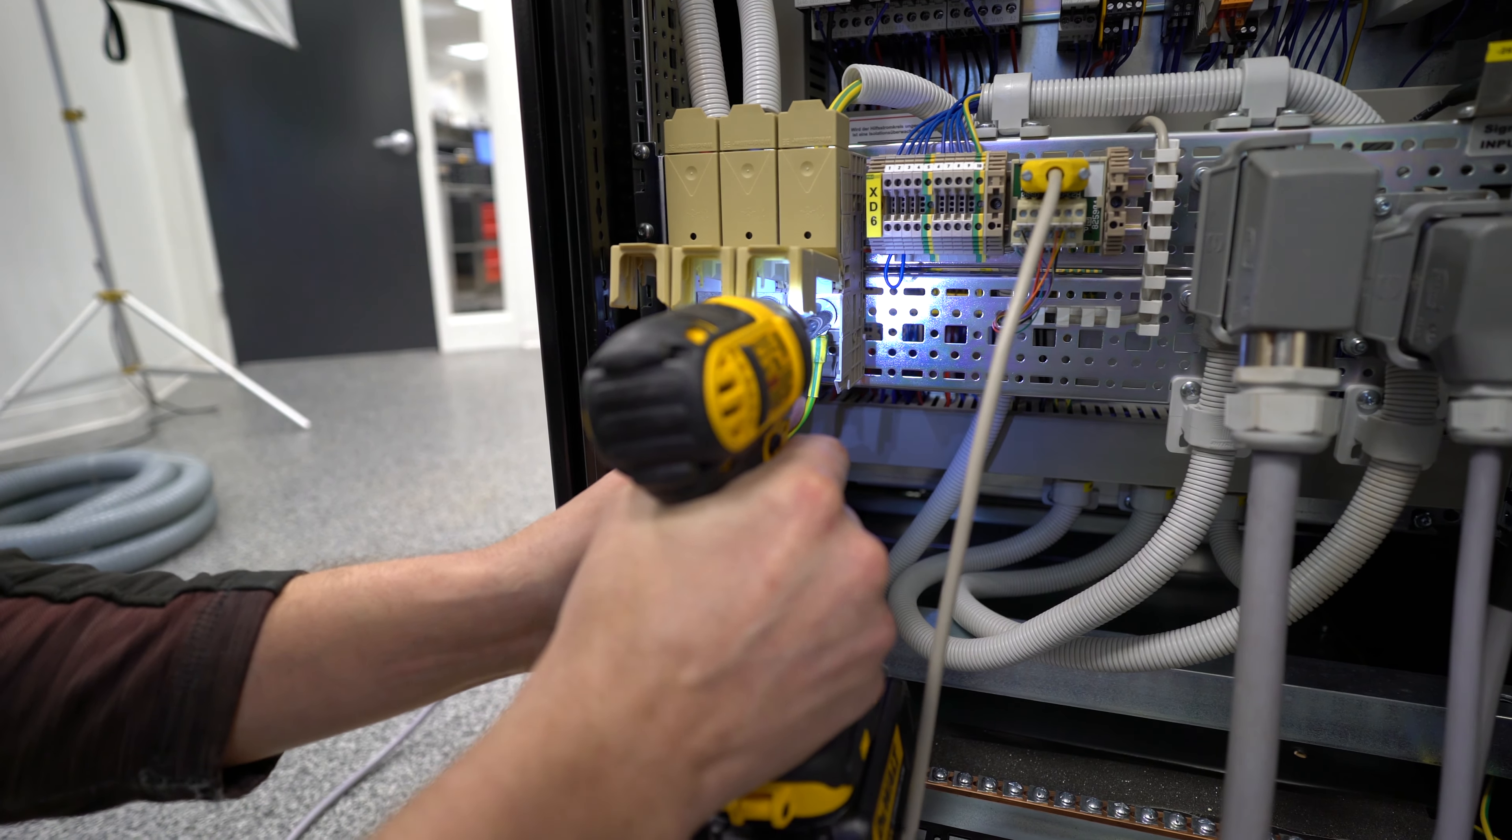To the back of the two controllers, connected the drive cable and connected the two ethernet cables over to a switch that we also installed in the back. So if you come around here, you'll see the network switch here. If you are only dealing with a four channel system, you will not require a network switch. In that case, feel free to run your network cable directly to the PC.